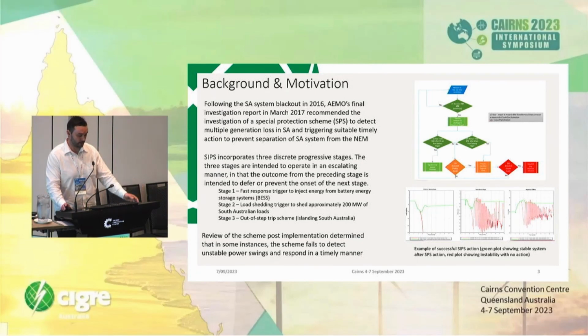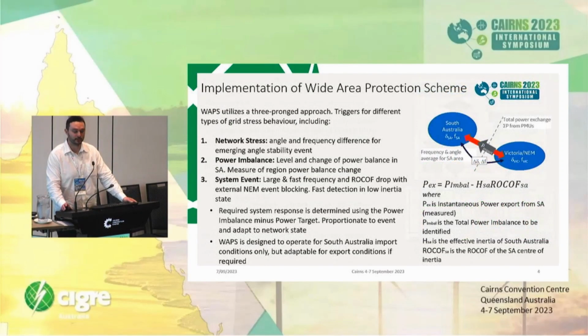This scheme works. There's been successful SIPS action in the past, but a reassessment of the scheme against an EMT model of South Australia found some shortcomings, particularly in maybe load shedding too much, or sometimes the stage 2, the power swing, not operating when it should have. So the next step was to review what other technology is available and how we could possibly upgrade the scheme. So that's when we embarked on this journey.